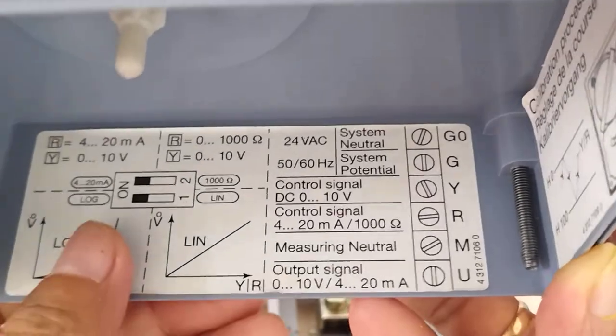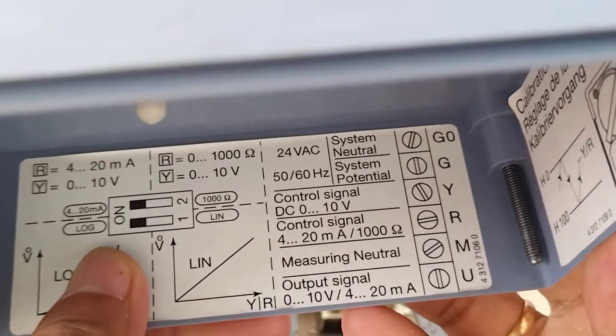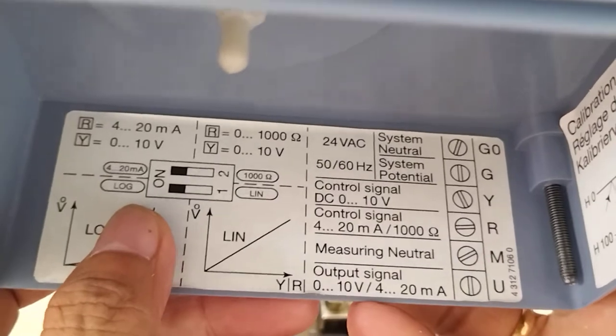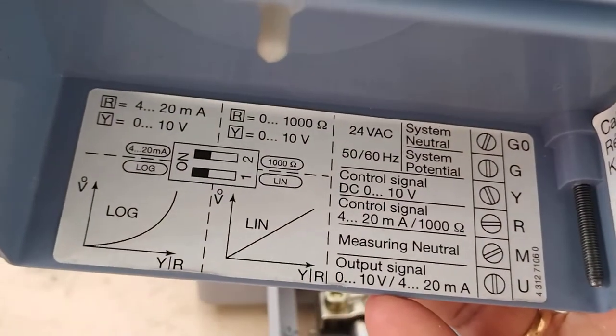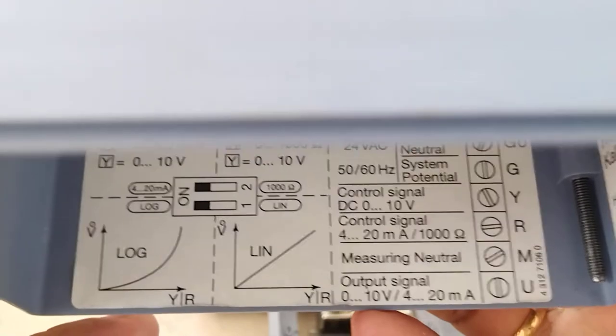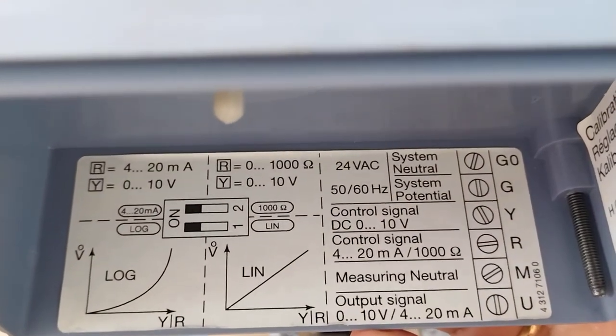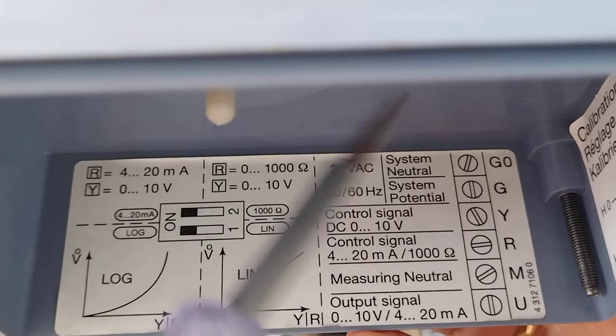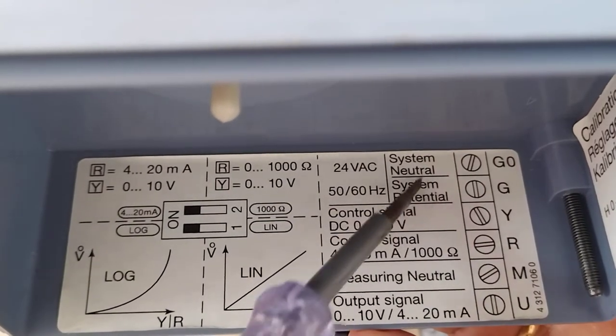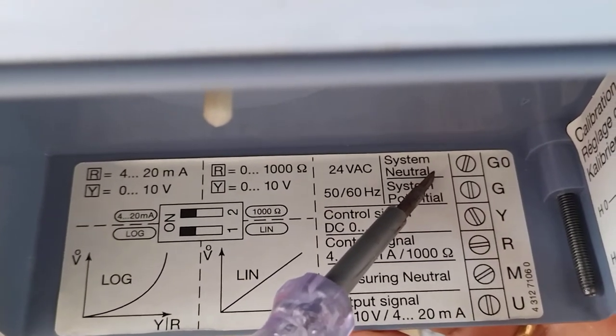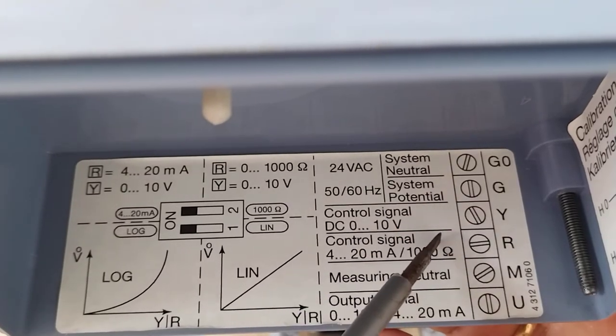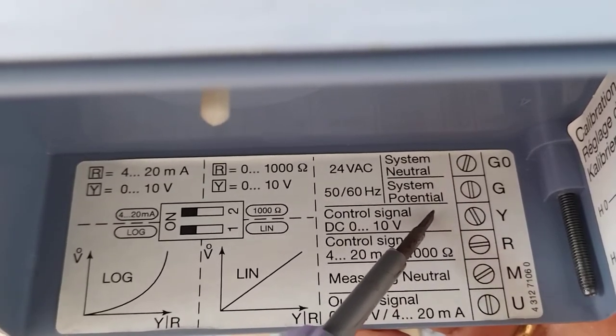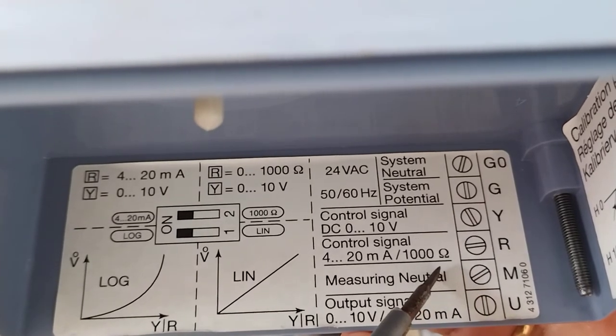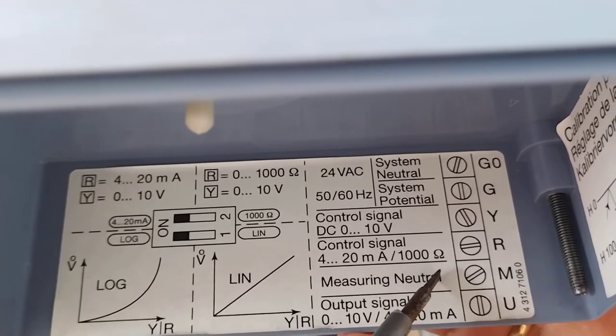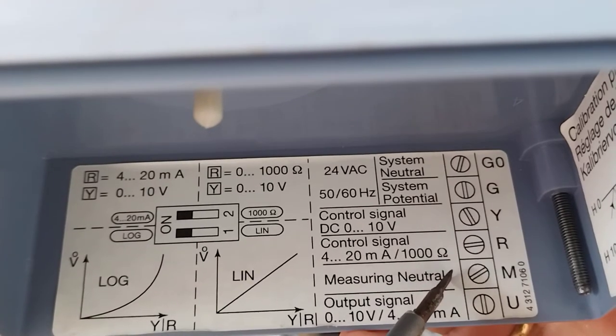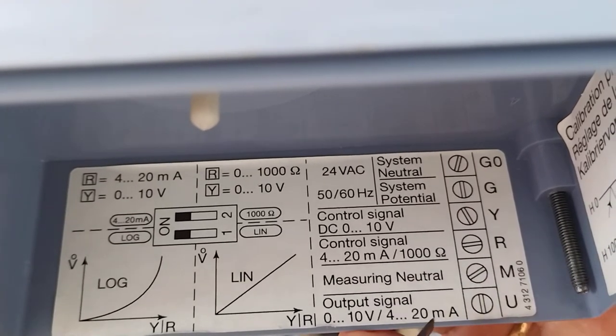Now guys, as a BMS engineer, one of your scopes is to pull cable, so you will ask your BMS team to pull cable for this. How many cables are you going to use? First, you will pull one cable, two core, for the power supply. Then one cable for the control signal, that will be Y, and the measuring neutral. Then one more cable for the output signal, for the feedback.